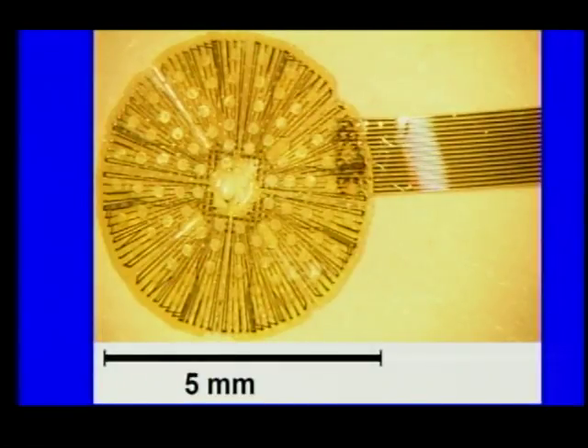So let me just give you an idea. We moved from the epiretinal side to the subretinal side because after 10 years of working on the epiretinal side, I decided that it just wasn't going to work. There wasn't going to be a way to conformally align the electrode array on the retinal surface. If you're separated by only 50 microns from the retina, only 50 microns, less than the width of a hair, you increase the stimulation thresholds fourfold. If you're doing surgery, you don't see that. It's hard to see 50 microns. So we wanted to be in complete contact with the retina over a wide area, which is a real challenge.